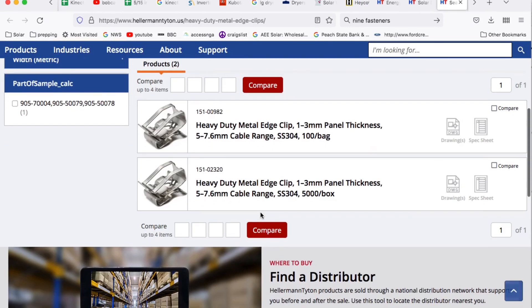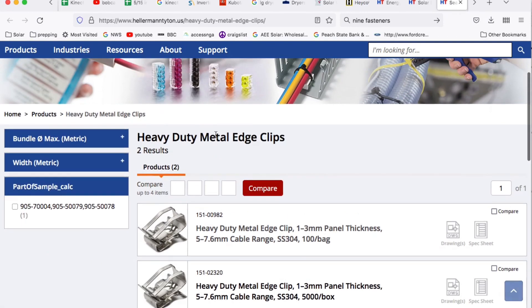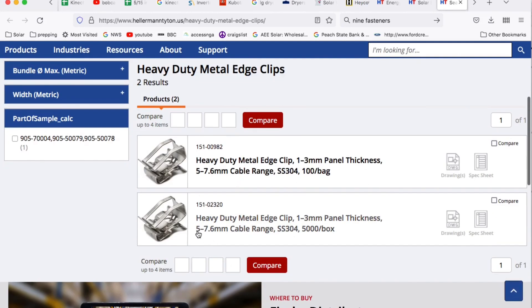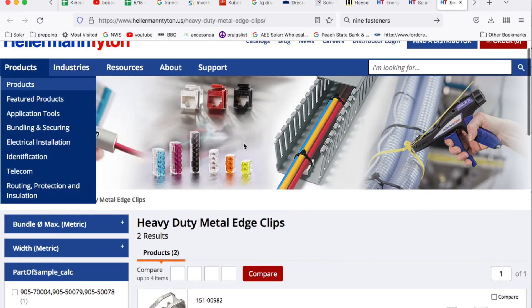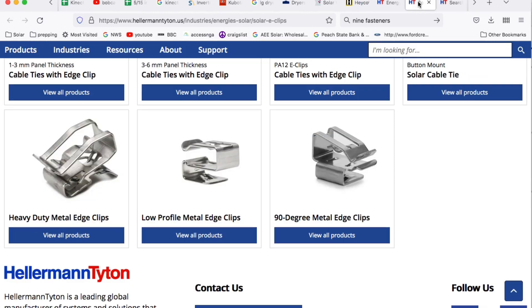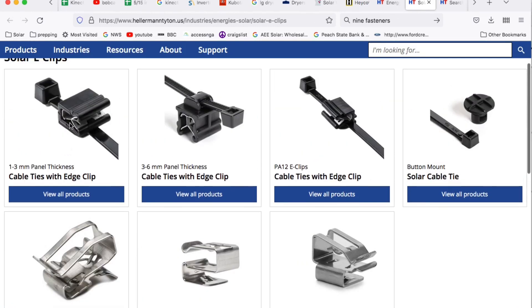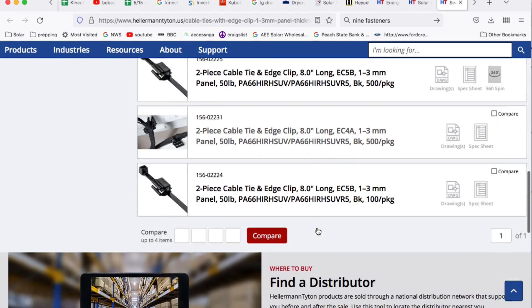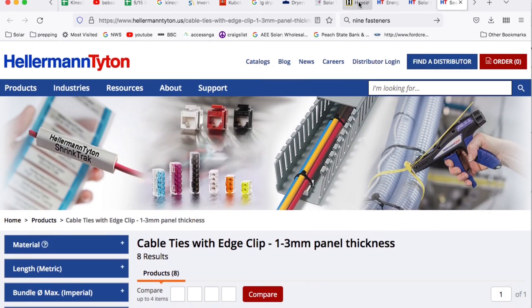I use this heavy-duty metal edge clip a lot, and it comes in a couple of different thicknesses. When you're using PV wire it's going to usually be the 7.6 millimeter cable; if it's 5 millimeter that is typically USE wire, which we used to use a lot more, but now with transformerless inverters it's almost all PV wire. They also have a lot of cable tie products, but I try to use the metal clips as much as I can. I might use zip ties just to hold things while I'm installing the metal clips.